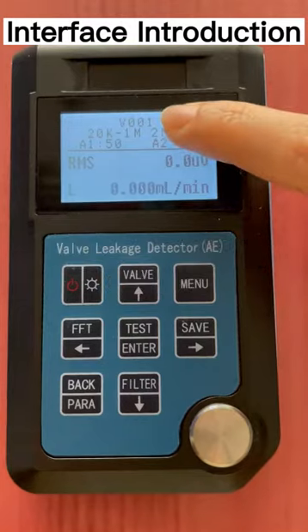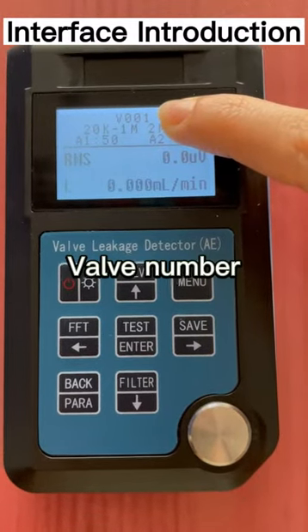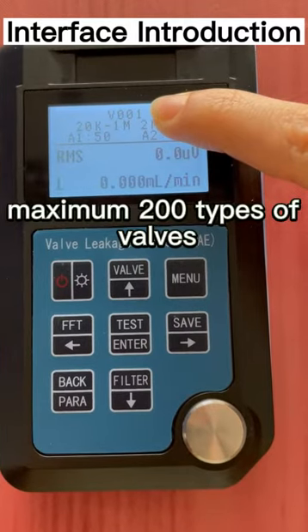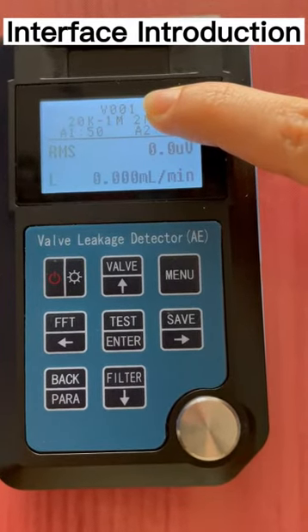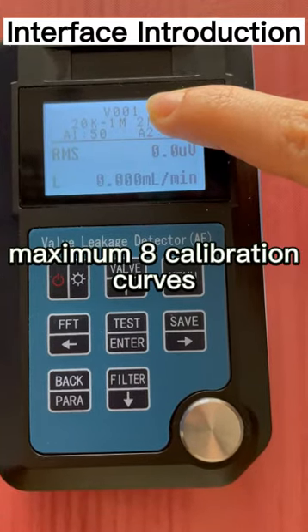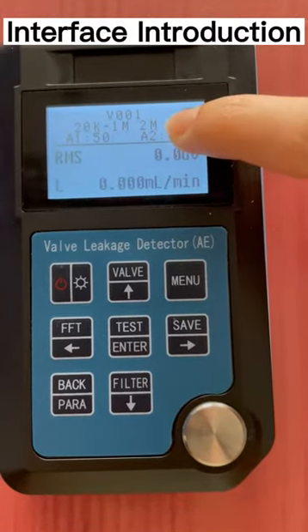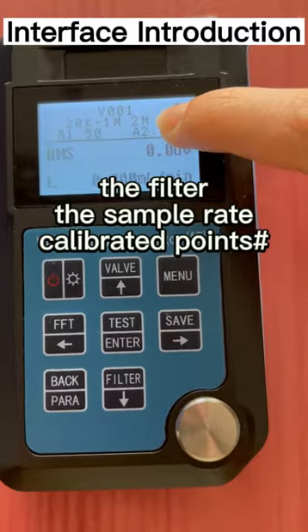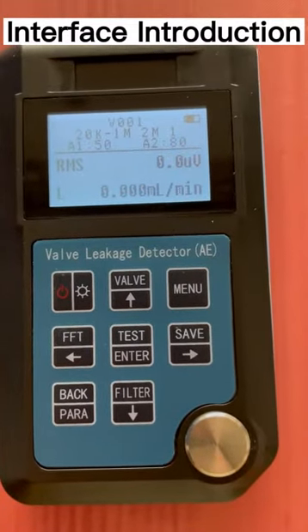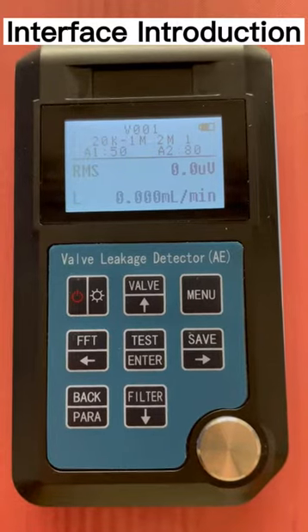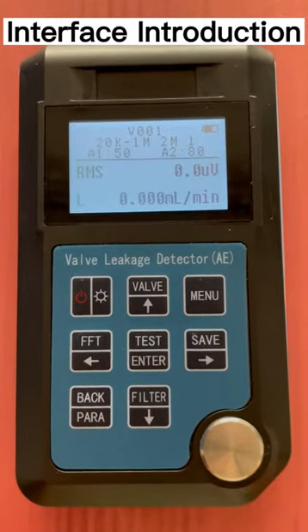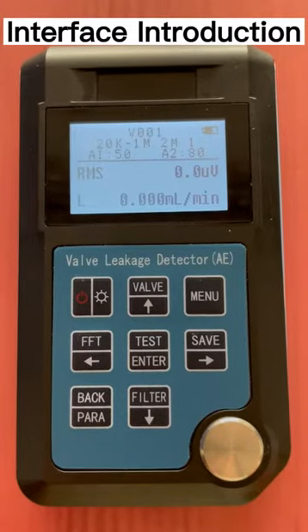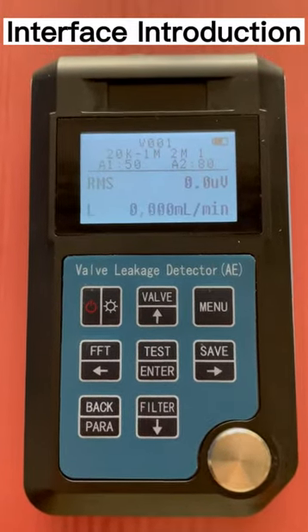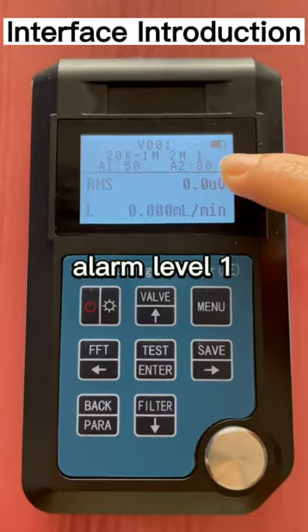The value on the top row of the screen is the selected valve number. A maximum of 200 types of valves can be set up, and each valve type can store a maximum of 8 calibration curves. The values on the second row are filter, sample rate, and calibrated points. Take the screen as an example. The filter is 20 kHz to 1 MHz. The sample rate is 2 MHz, and there is 1 calibrated point. On row 3, A1 means alarm level 1, and A2 means alarm level 2.